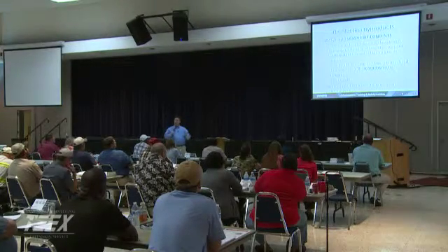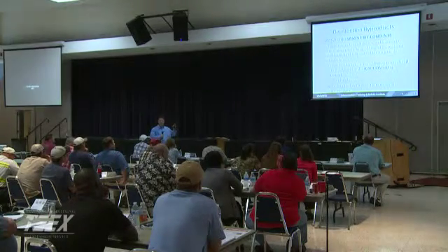All right, I was corrected by somebody yesterday. Apparently, this is not the type of sample bottles that you use here, or at least that's not what somebody used yesterday, and they told me that this was wrong. These specific ones were written for the most common setup for collecting samples. Generally, you'll have two 40 milliliter vials, two 2 milliliter vials, and one 250 milliliter vial. Now, some systems we found have gone to collecting just a larger sample and then letting the lab split it up as they need it.